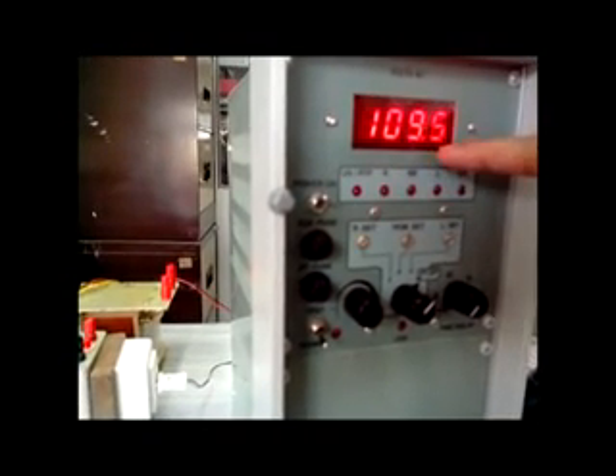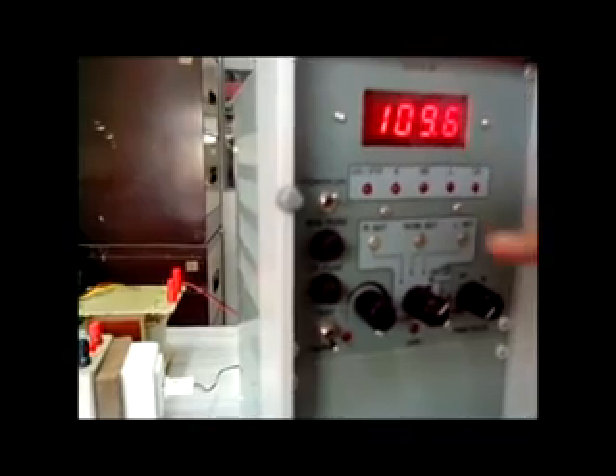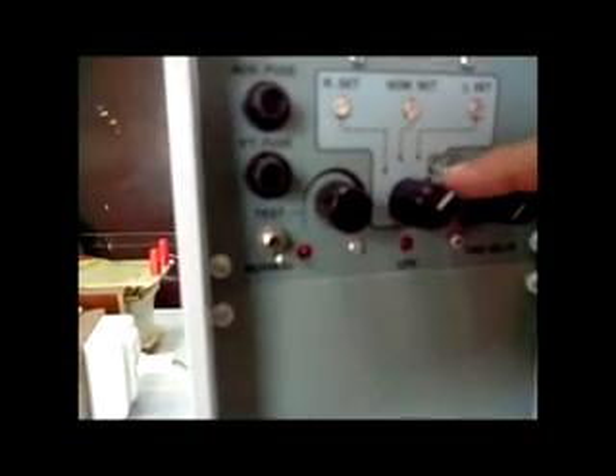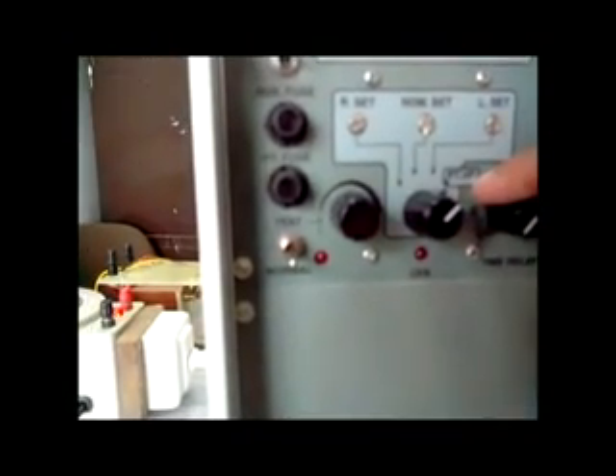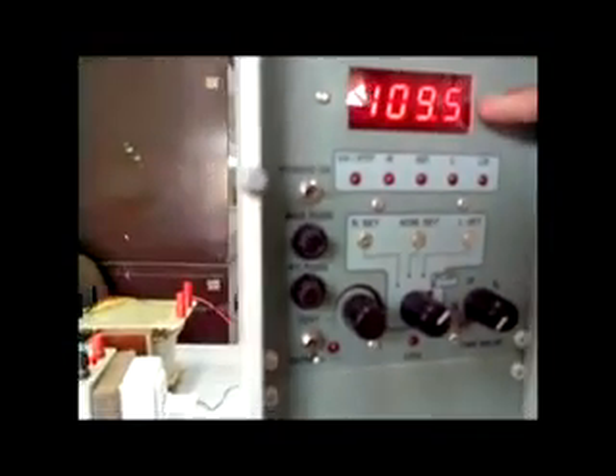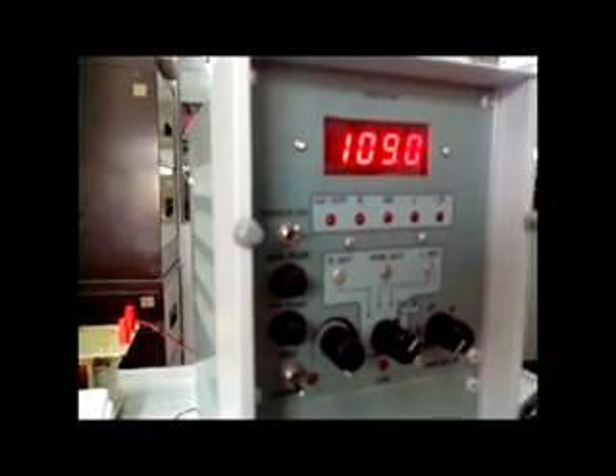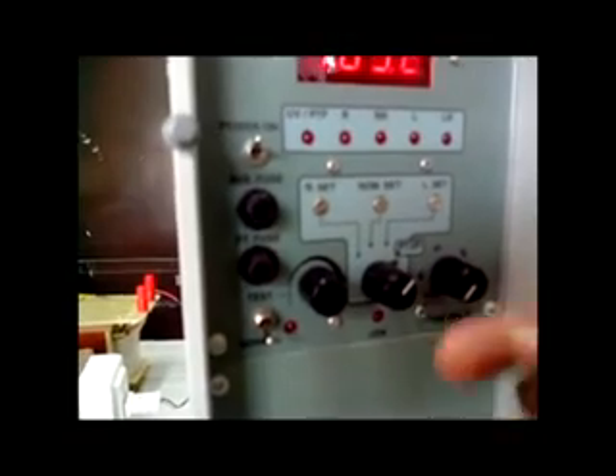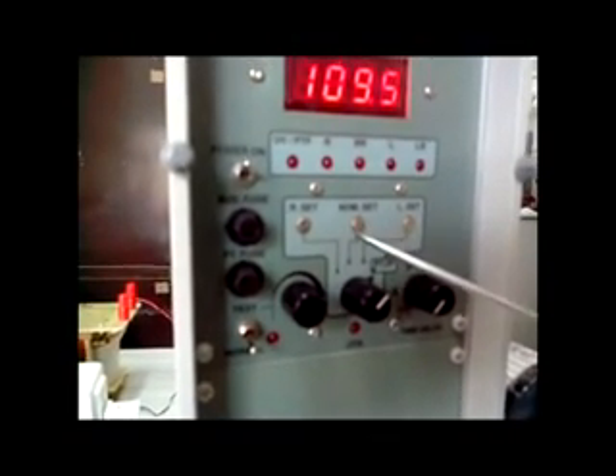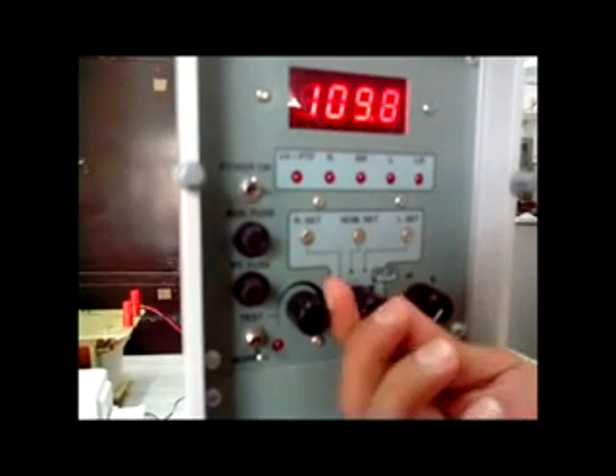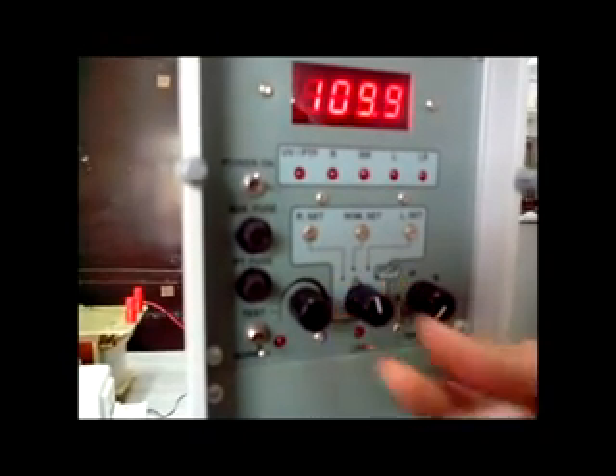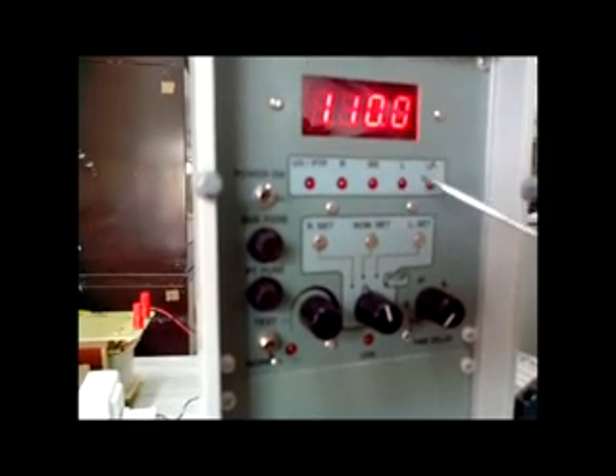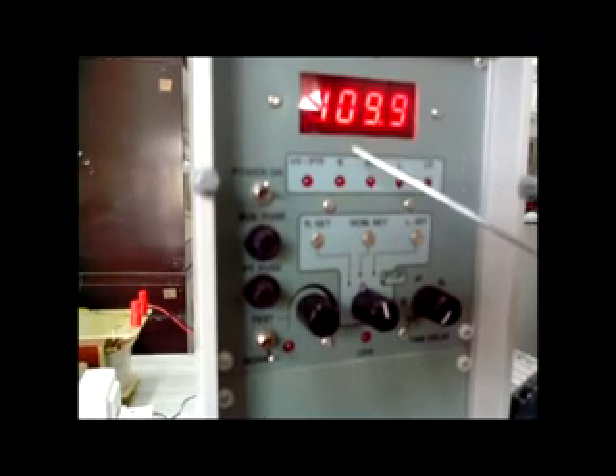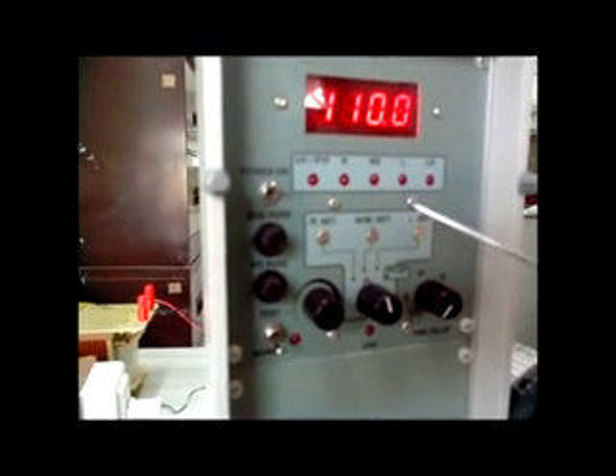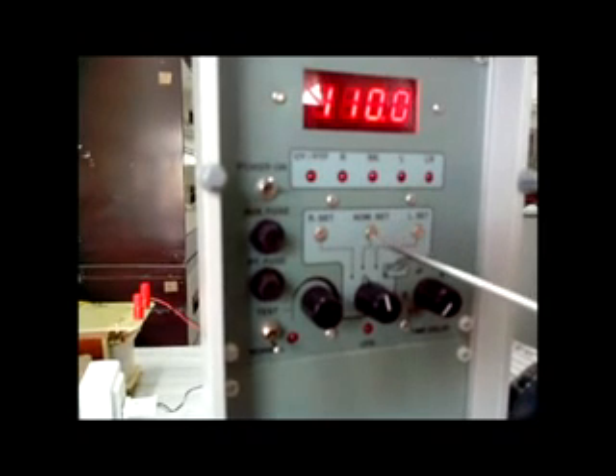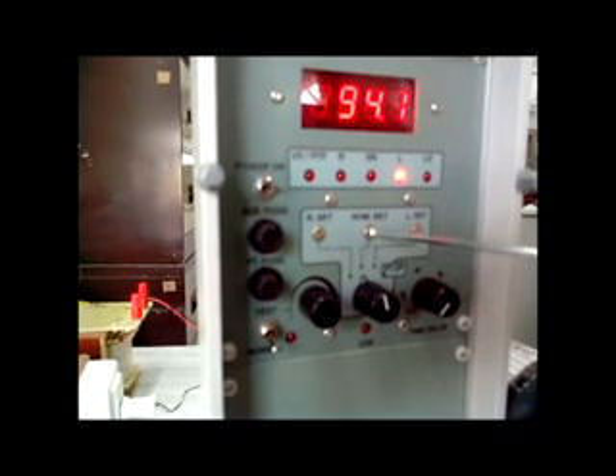This is the PT voltage as the selector switch is in the PT input direction. It means the display will show PT input voltage only. Now we check the setting. For setting, first of all we have to set the nominal set. For this, the nominal set pot is provided. Then we keep the selector in the nominal set position. Now the display shows the nominal voltage. Presently the nominal voltage is 110 volts by default. The range of nominal voltage is plus minus 10%; by moving the nominal setting pot, variation of the voltage display is observed.